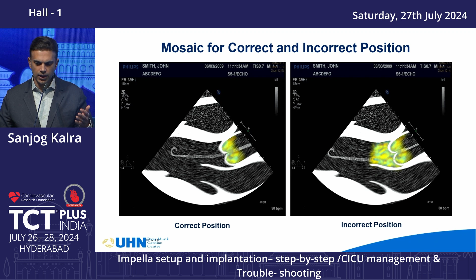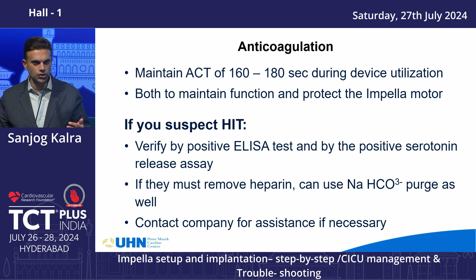From an anticoagulation piece, you aim to maintain between 160 and 180 ACTs. That's usually a PTT of about 60. And if you suspect HIT, verify it because it's a rare problem. And if you have a problem where you have to pull the heparin, you can use sodium bicarbonate as your purge. You do not need to put them on systemic heparin in those situations, as long as the device is functioning at a level of P6 or higher.